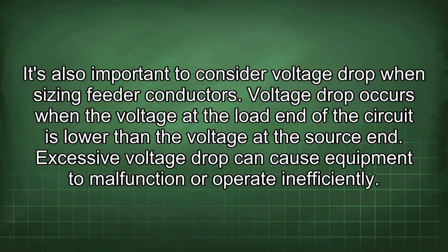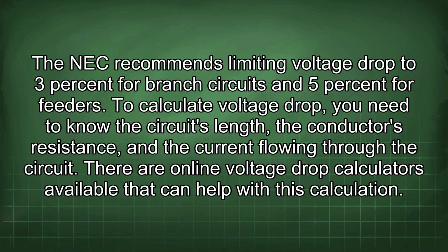It's also important to consider voltage drop when sizing feeder conductors. Voltage drop occurs when the voltage at the load end of the circuit is lower than the voltage at the source end. Excessive voltage drop can cause equipment to malfunction or operate inefficiently. The NEC recommends limiting voltage drop to 3% for branch circuits and 5% for feeders. To calculate voltage drop, you need to know the circuit's length, the conductor's resistance, and the current flowing through the circuit. There are online voltage drop calculators available that can help with this calculation.